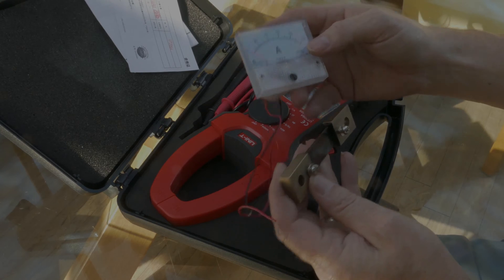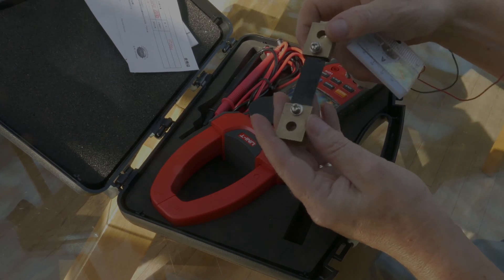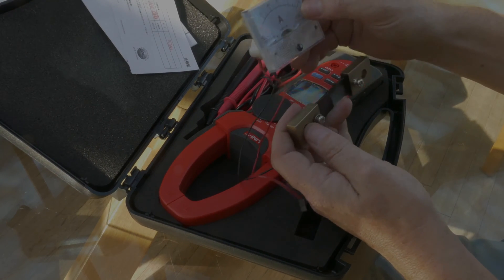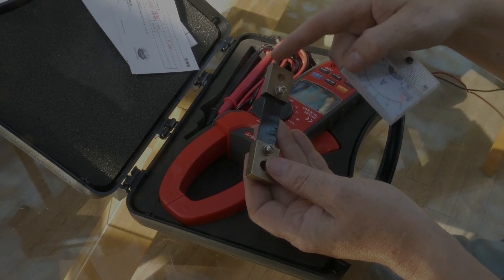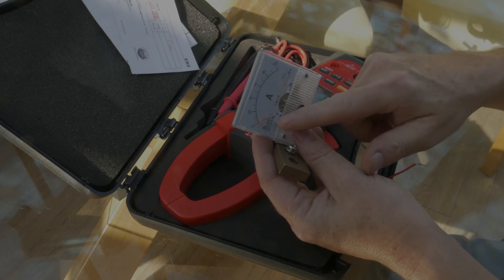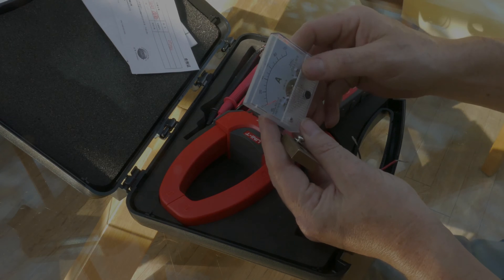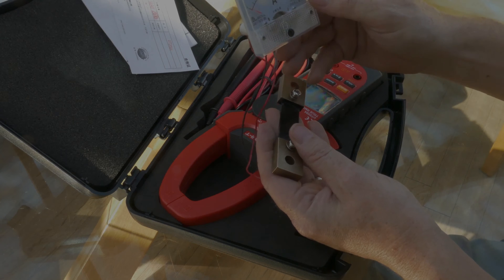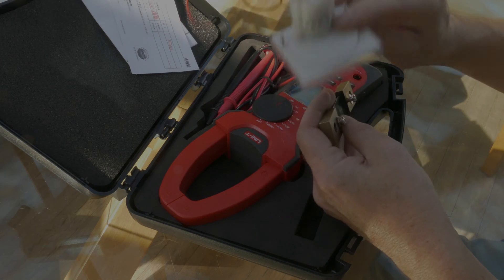Again, just like in your multimeter, except this can handle up to 100 amps. This is a known value resistor matched with a 75 millivolt maximum throw voltmeter. Now, when 100 amps flows through this shunt, the voltage drop across the two terminals is 75 millivolts. And yes, using magnetism, it throws it to the right, measuring the millivolt drop. 75 millivolts will give you 100 amp reading. And that's right, even ammeters are actually voltmeters, and voltmeters ultimately use magnetism.